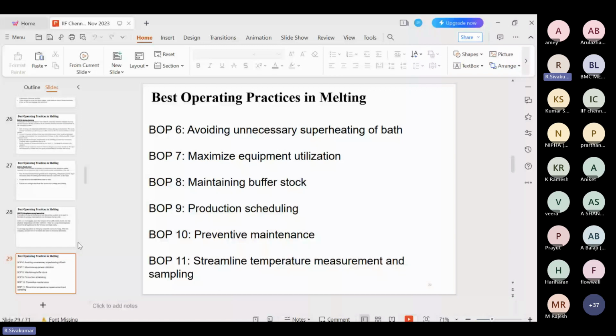So it should be followed. For the coil cooling and panel cooling, water temperature and flow rate should be monitored on an hourly basis. Also, at least twice in a shift the values should be noted. The panel must be checked on a weekly basis, and cleaning must be done on a monthly basis. Check the condition of the cooling tower also. These are the additional things to be followed in the auxiliary area. Otherwise, if anything fails in the auxiliary area, the furnace goes idle. Because of any pump failure or cooling tower issue, there is breakdown time, and the furnace is forced to stop. So all the auxiliary equipment associated with the furnace should be kept ready, and all the maintenance activities should be done.